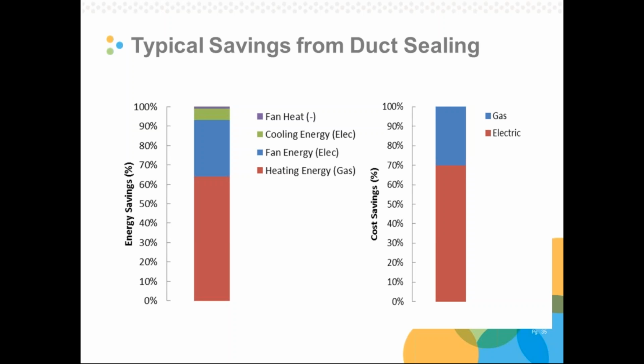A note on that: we have a very hard time distinguishing between 0 and 1% leakage. It pretty much pushes the limits of our research, so we say 1% conservatively on final leakage. Anyway, we have 4 contributions to energy savings here on this sealed duct. The majority of the saved energy is from the heating side. So by preventing somewhere around 3 to 4% of the energy from the heating coil from leaving the building, we save 64% of our total energy savings in gas.